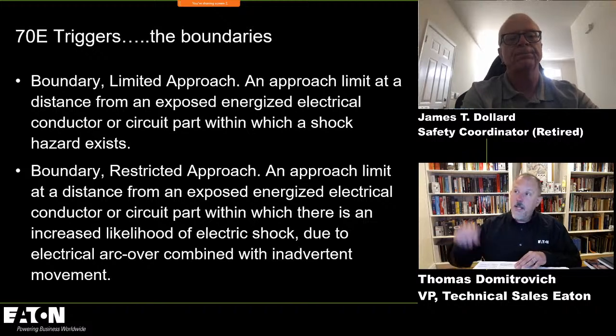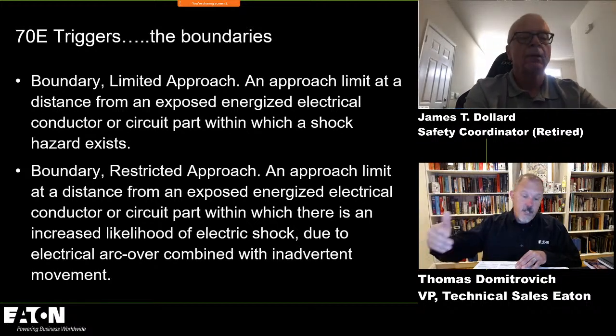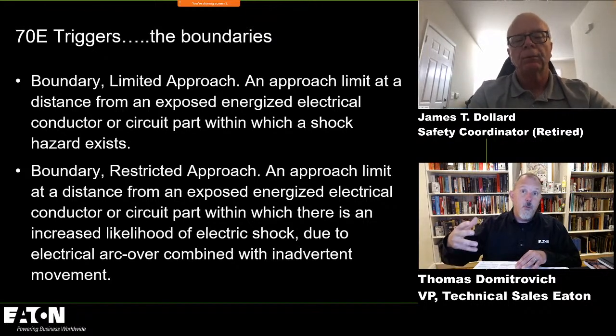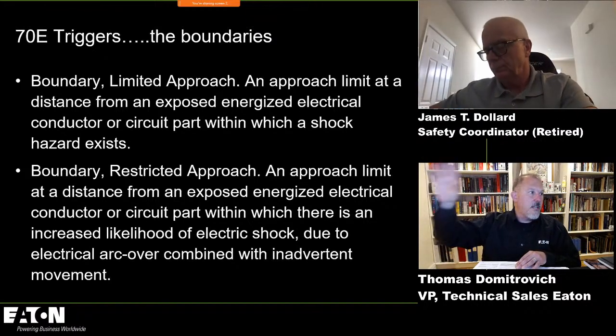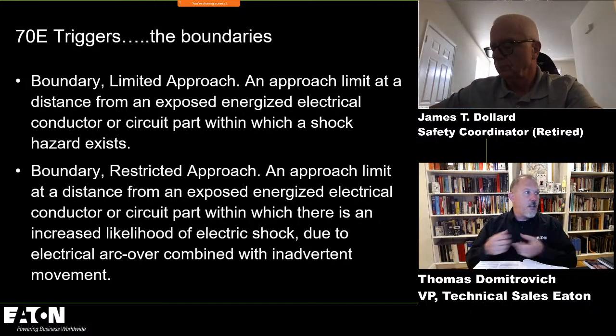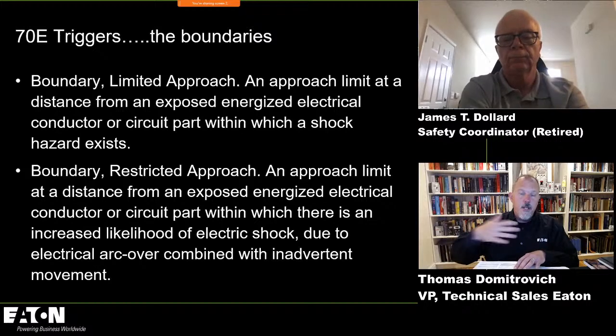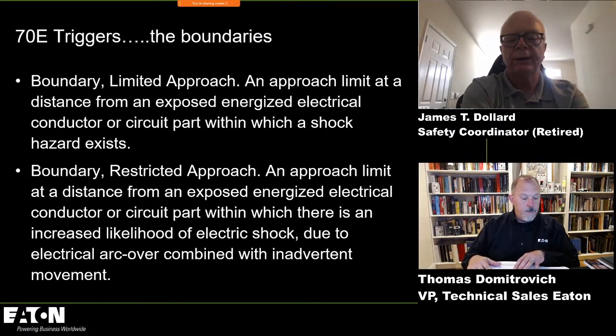Now, for the limited approach boundary, they put 2 different distances. One is for exposed movable conductors and the other is for exposed fixed circuit parts. The movable ones are like your outside lines, anything that is not secured down, energized parts that might sway with the wind. That's right. The very first column has a little superscript C at the end of it, and when you go down to the bottom, just like you said, Tom, that's overhead conductors pole to pole. We're just not doing that work, so we're always using the third column. Excellent.